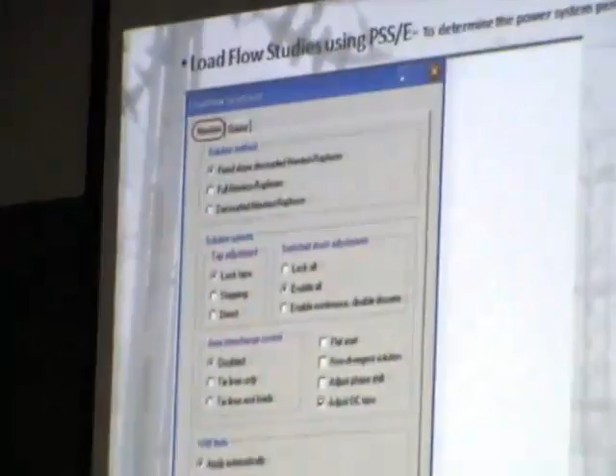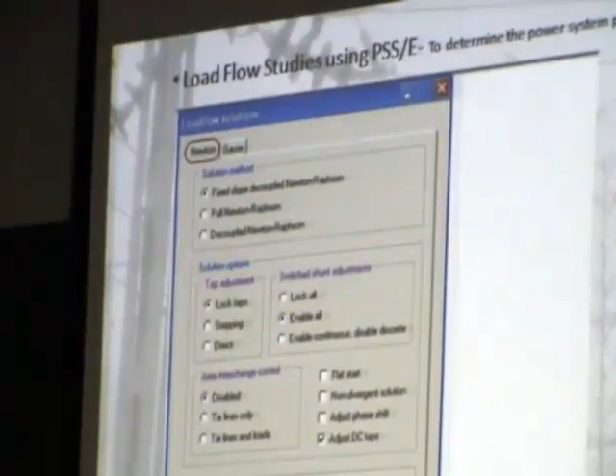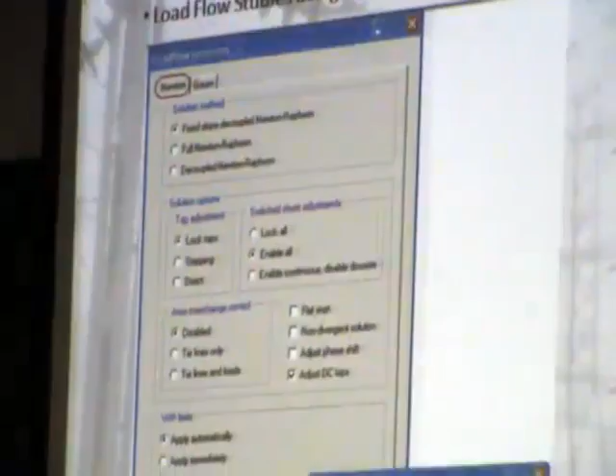When we model the power system using PSSE, we have several components in the power system, normally bus bars, branches, loads, machines, transformers, switch shunts. They are the basic transmission equipment in our system. The load flow study, normally we do that to determine the power system performance in steady state. For that, as you know, we have two methods, Newton-Raphson and the Gauss method. In PSSE we have three Newton-Raphson methods, and for the Gauss-Seidel we have two methods. We can use them in different conditions. Normally Newton-Raphson is used for the normal conditions, and where we have some voltage problem and it is difficult to solve, then we use the Gauss-Seidel.